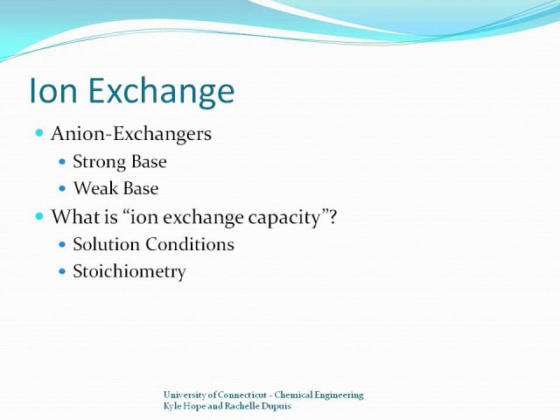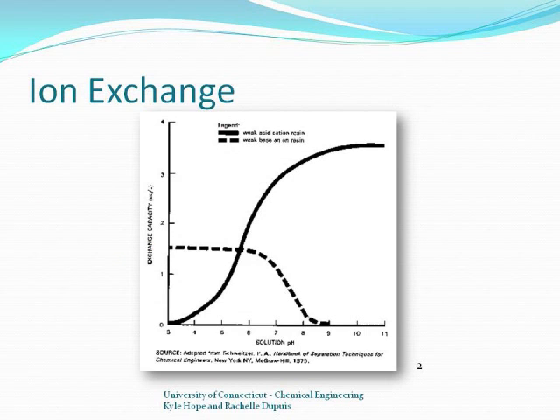Similarly, exchanging for a +1 ion like potassium would create an even ratio. This is the concept of exchange capacity, and strong acid cation exchange resins have an exchange capacity independent of solution pH. On the other hand, the exchange capacity of weak acid cation exchangers does depend on solution pH. The graph on the screen shows the effect of solution pH on exchange capacity for both weak acid and weak base exchange resins. Weak base and strong base anion exchangers exhibit behaviors similar to those substances.